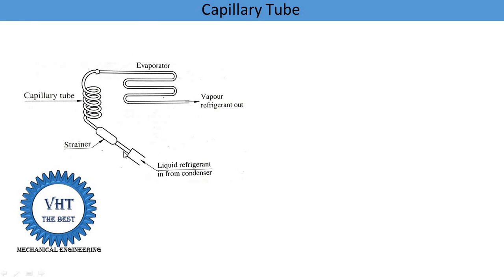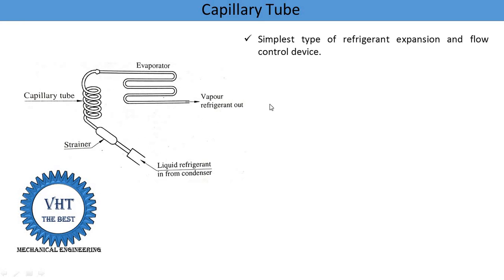The capillary tube is installed between the condenser and evaporator, and it is used to reduce the pressure of the refrigerant from condenser pressure to evaporator pressure. The liquid refrigerant coming from the condenser is supplied inside the capillary tube, where pressure is reduced. After pressure reduction, it is supplied into the evaporator.